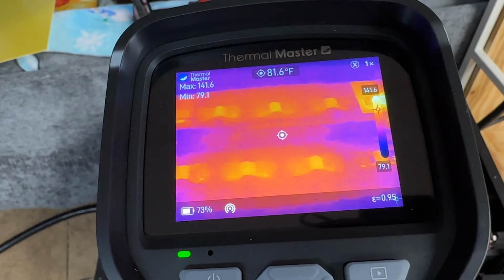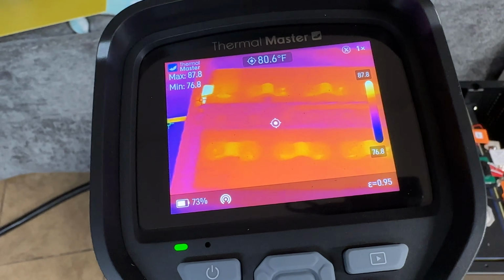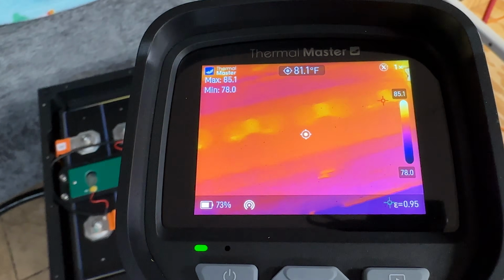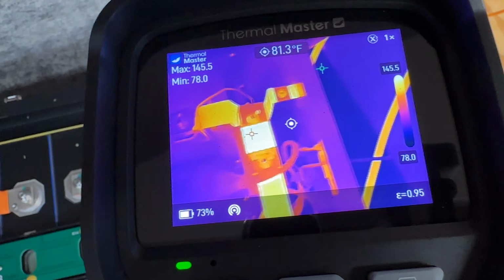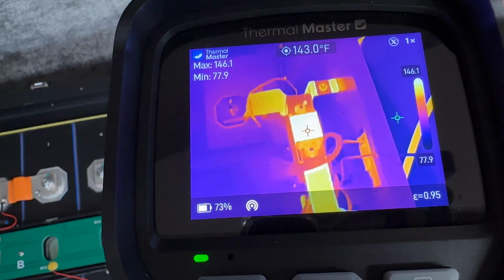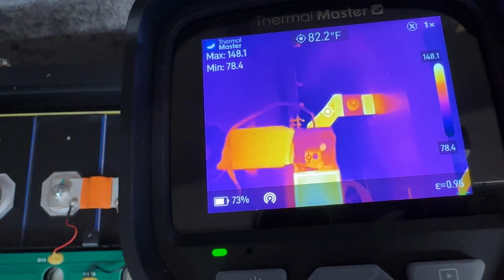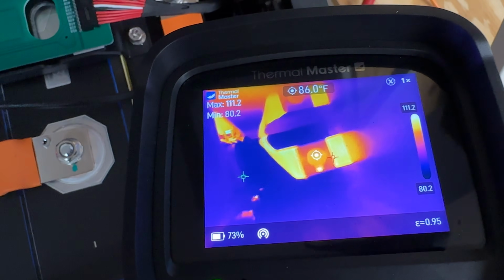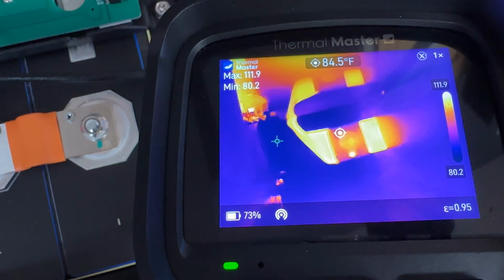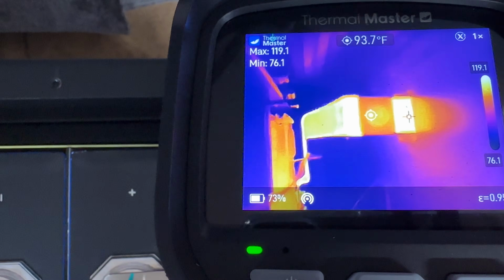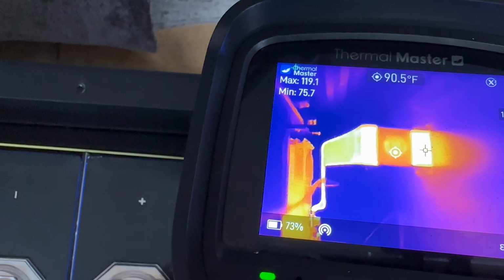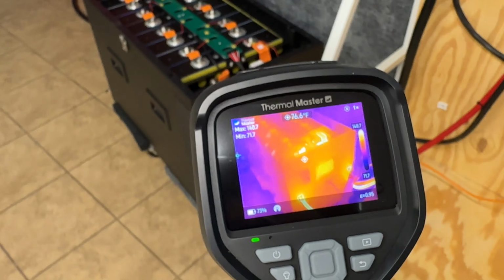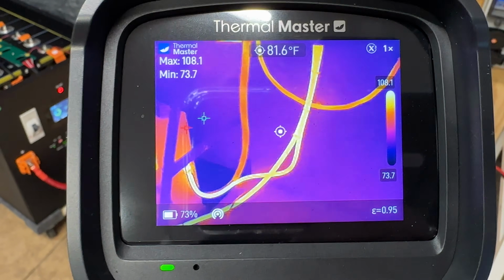That's really nothing. You can tell the bus bars are slightly warmer than the surrounding environment, but the cells themselves are still cold. This fuse right here has a little bit of heat on it, about 140 degrees, and that really looks like the hottest part of everything. Our main positive connection is at 90 degrees, main negative about 90 degrees as well. Our BMS down there is looking nice and happy, about 97 degrees. Everything seems really good, and you can even see the cables kind of going a little bit as well.